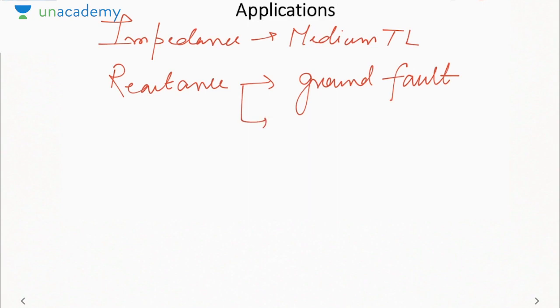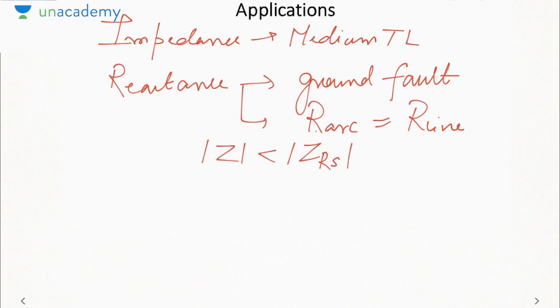The other thing is that whenever the circuit breaker operates, there will be arc resistance. If arc resistance is approximately equal to line resistance, then the relay will maloperate. Why? Suppose we take the impedance relay; the condition is mod Z less than mod ZRS. But due to the resistance of the arc, the resistance gets doubled, so impedance increases. If impedance increases, there is a chance that mod Z will be greater than mod ZRS. If such a thing happens, the relay will not operate. But there was a fault. So in that case also we need a relay which is insensitive to resistance.